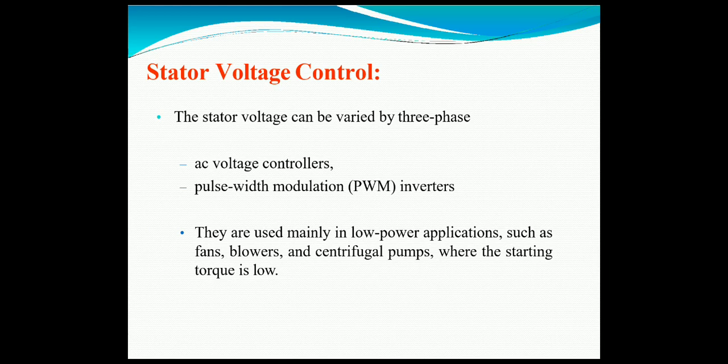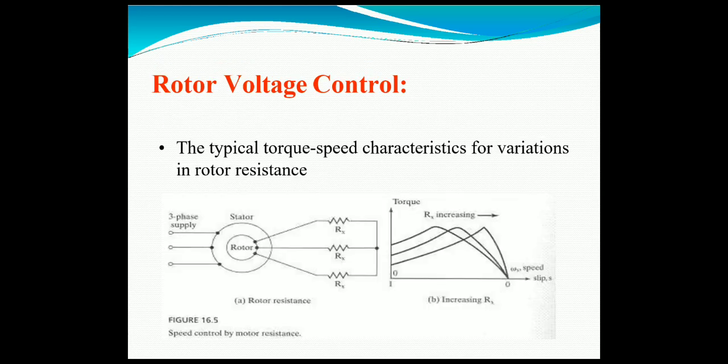For stator voltage control, the stator voltage can be varied using three-phase AC voltage controllers and also with PWM — pulse width modulated — inverters. These are mainly used for low-power applications like fans, blowers, and centrifugal pumps.